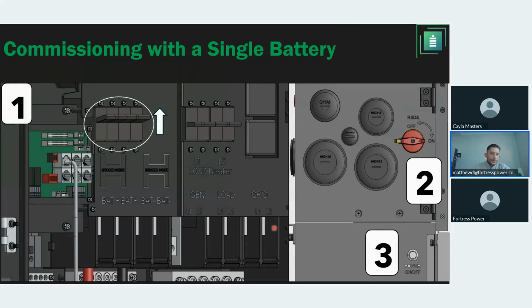Commissioning. Simple steps. Turn the battery breaker at the inverter side, right? And we always say that because regardless of any inverter or disconnect you may use, when you're doing it the other way around, energizing the battery and then flipping the breaker, you might create arc issues or that might or might not affect. We haven't seen that necessarily on the Envy, but I always recommend doing it just for safe practice. And it's a standard practice, right?